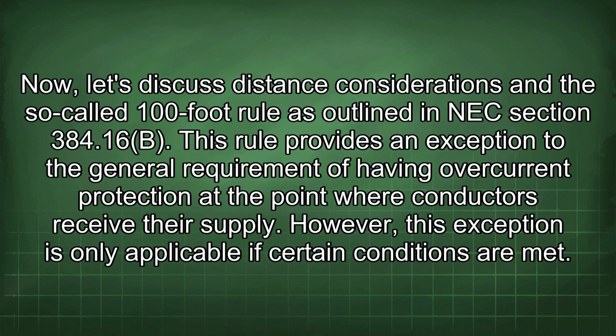Now, let's discuss distance considerations and the so-called 100-foot rule as outlined in NEC Section 384.16b. This rule provides an exception to the general requirement of having overcurrent protection at the point where conductors receive their supply. However, this exception is only applicable if certain conditions are met.